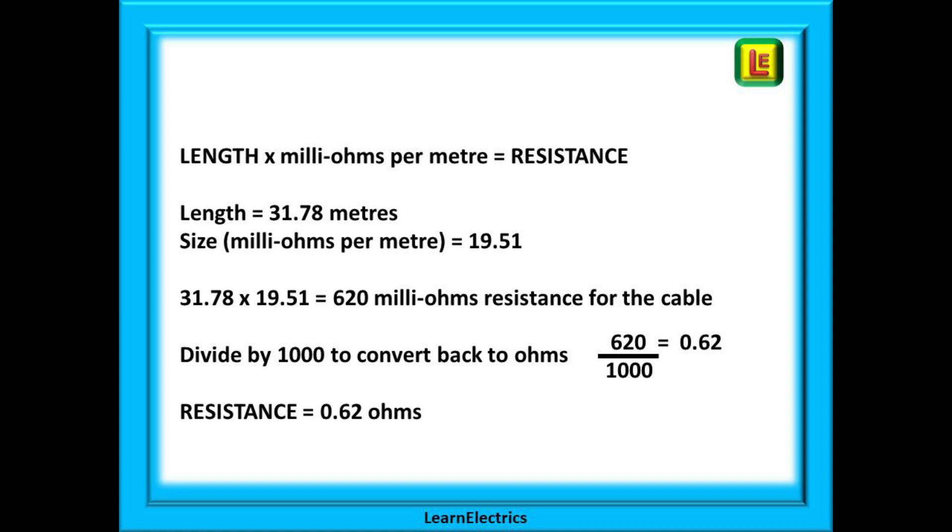We have 31.78 meters and we have 19.51 milli ohms. Multiply them together. 31.78 multiplied by 19.51 gives us 620 milli ohms. The resistance for the cable. Divide this by 1000 to convert it back to ordinary ohms and we have 0.62 ohms. And this is the number we started with just a few slides ago.